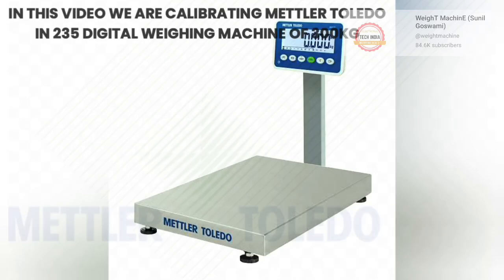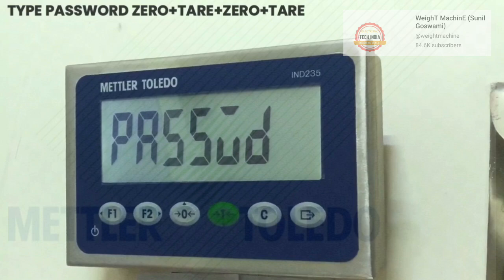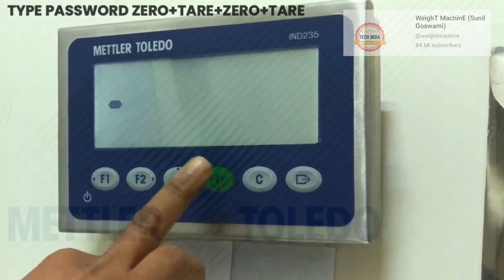Welcome to the video guys. In this video we are calibrating a Mettler Toledo IND 235 electronic weighing scale of 300 kg. Press and hold the enter button for 10 seconds, then type password zero, tare, zero, tare.